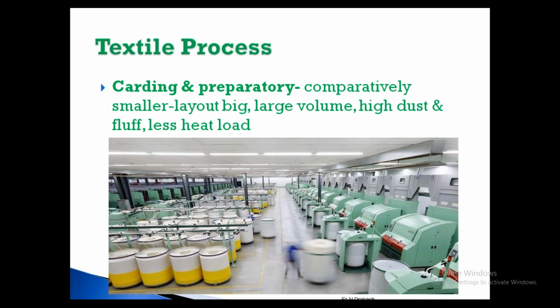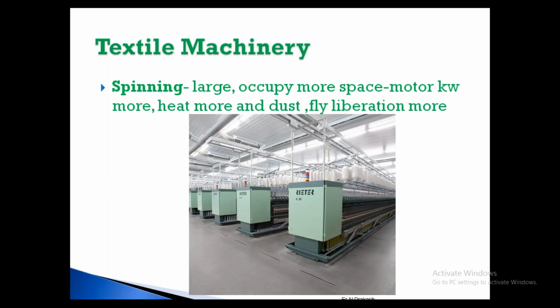In spinning preparatory, that is including carding, comber, everything, the machines are comparatively smaller, but the layout is big with a large volume. It has high dust and fluff. Heat load is comparatively less, and machine motor kilowatt is less compared to blow room. Then spinning: if you take spinning textile machinery, it is large and occupies more space, more kilowatt, and it generates more heat, dust, and fly liberation, everything more. Once everything is generated more, obviously we have to maintain a better inside condition. Heat is also generated more, so we have to dissipate that heat and maintain the required RH and temperature as per the recommended RH and temperature.